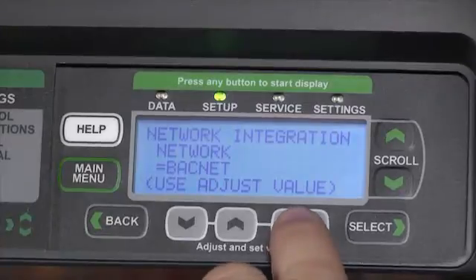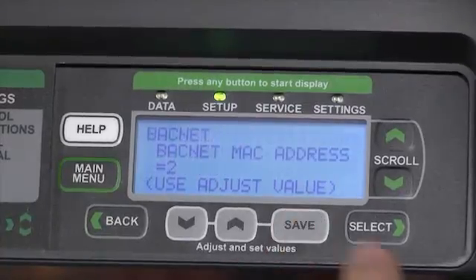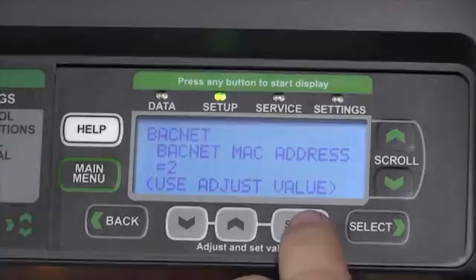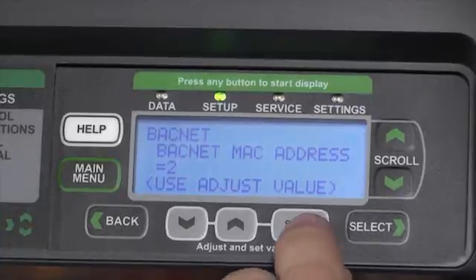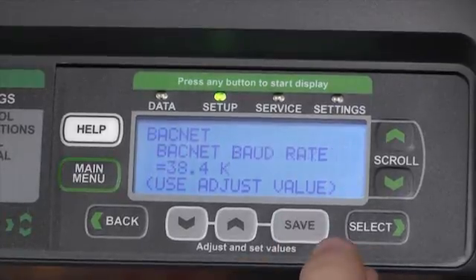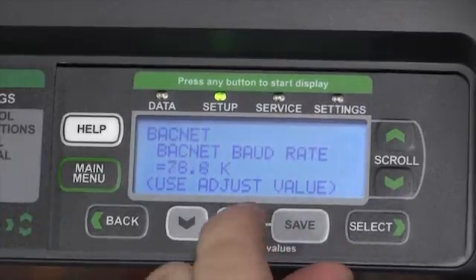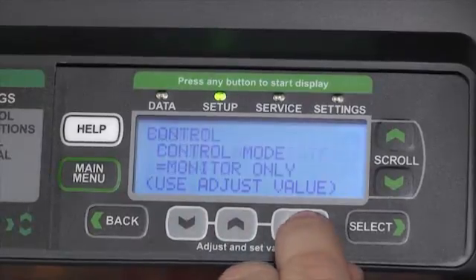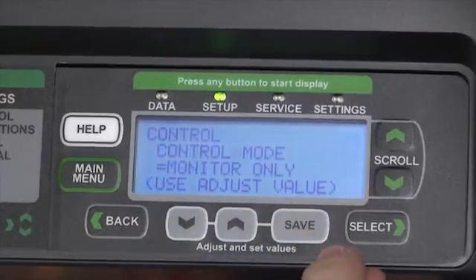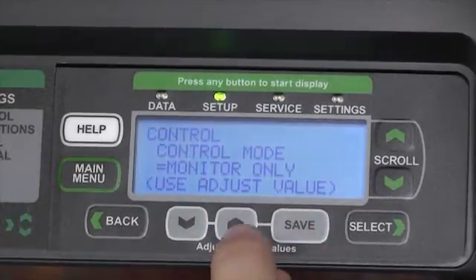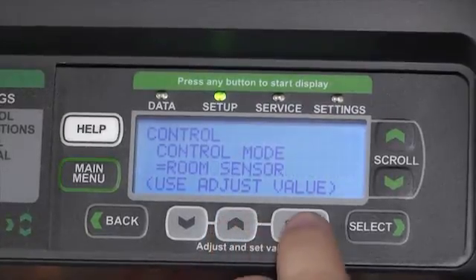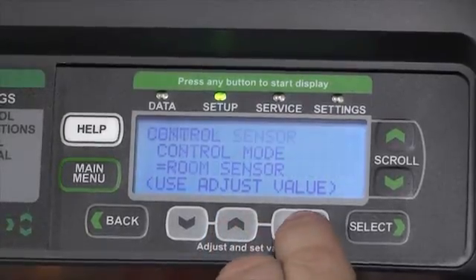Pressing the Save button will lock in the value and take us to the next screen, where we'll set our MAC address, our baud rate from the variable selections available to us, and our control mode — whether it's monitor only, a network thermostat, or a room sensor.